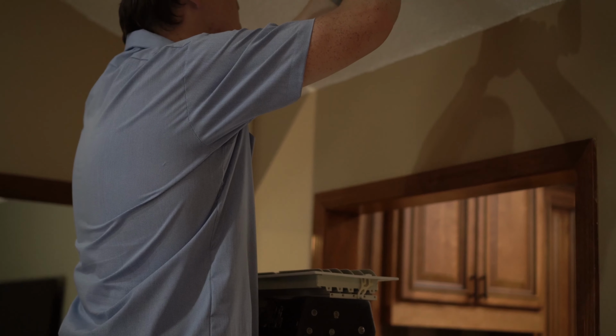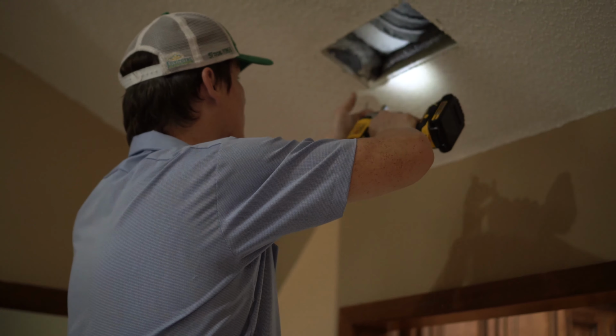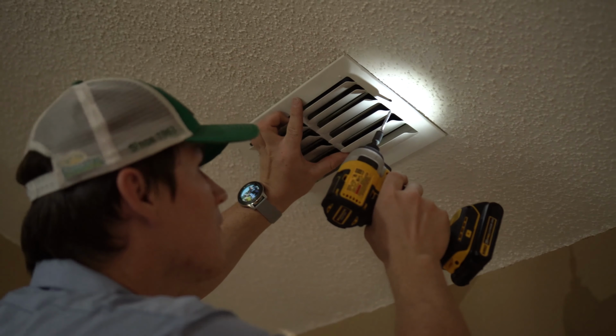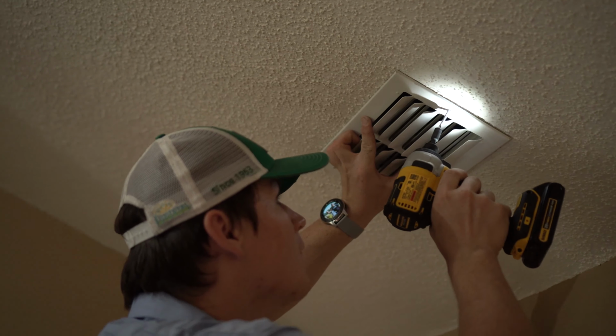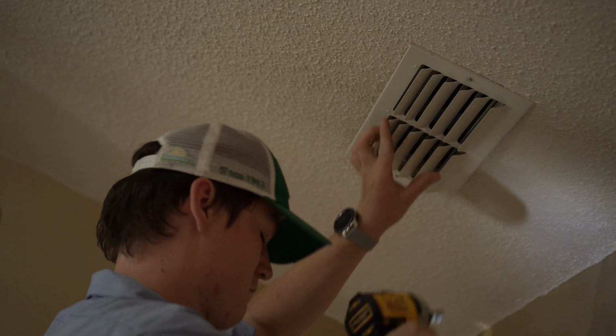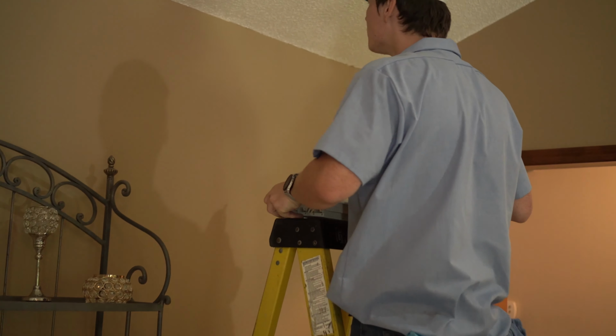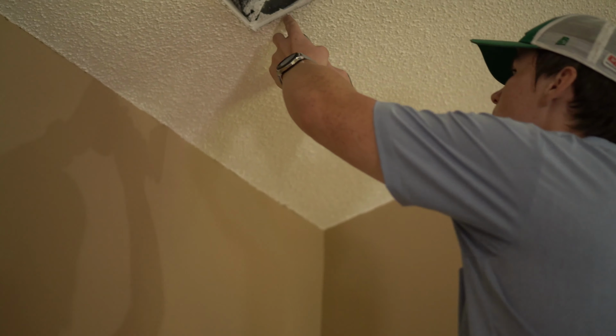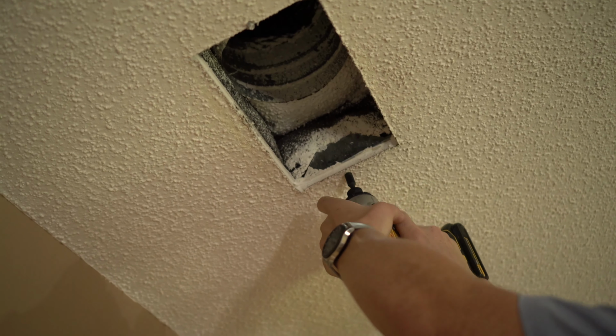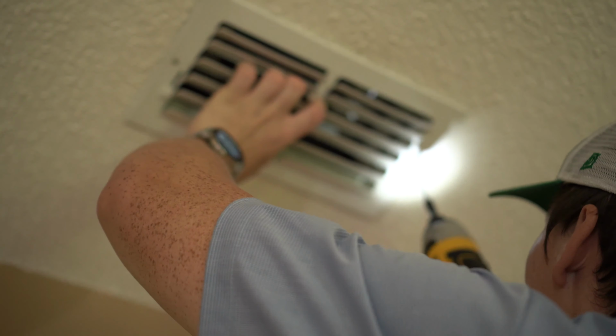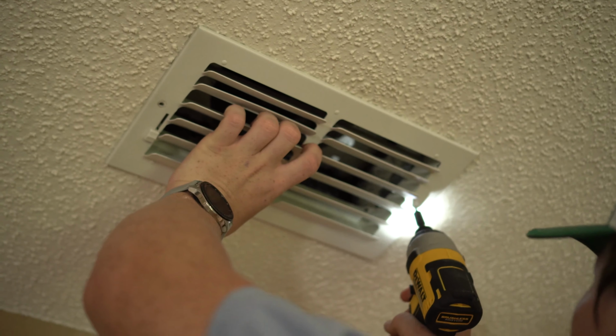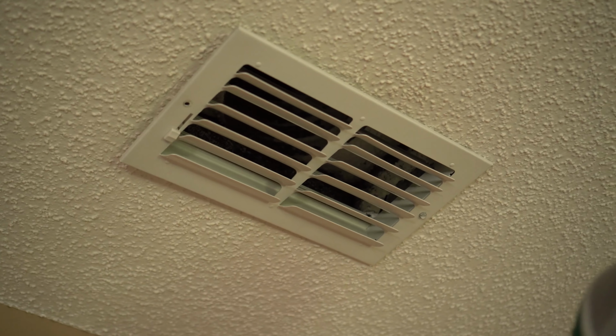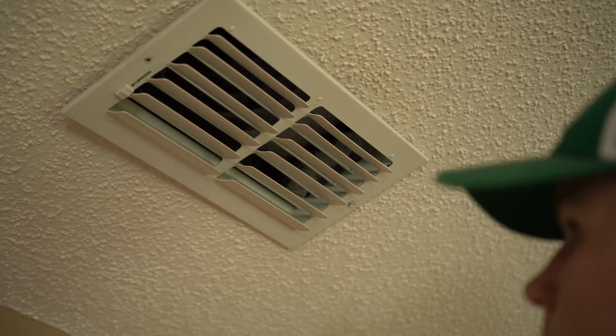When installing vents, please note that over-tightening will lead to an unsatisfied client and unhappy lead technician. Since this is the most seen portion of the system, they will be very unhappy with bent-up vents. On the air handling unit, please replace any rusted screws and make sure they are all the same. On vents, when possible, replace all screws with quarter drive 2-inch white screws in order to remain uniform.